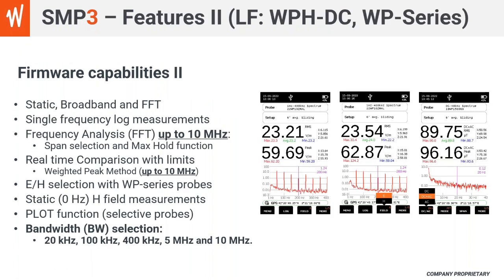Then for the low frequency probes, you have the WPH DC probe and the WP series probes. These probes allow you to do static field measurements, broadband and FFT measurements, as I talked about before, but they also allow you to do single frequency logging. In the case of frequency analysis, you can do measurements up to 10 megahertz using the WP10M probe. It also allows you different span selections to have different resolutions in the FFT.